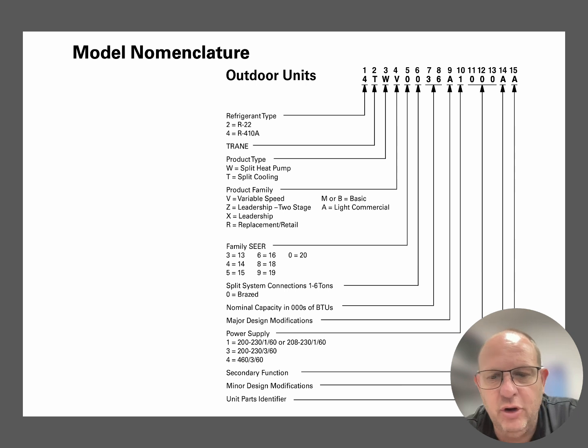The one thing that I really want to pay close attention to on the model numbers is the tonnage of the actual unit. And that's why it's important for us to look at these units and to distinguish between different tonnages of units that are out there quickly by looking at these numbers. So we're looking for multiples of 12. And if we were to look at this particular one, we're looking right in this, and that's 7 or 8 on these systems. And we're looking at 4TWV0036. The 36 tells me that this is a 3-ton unit.